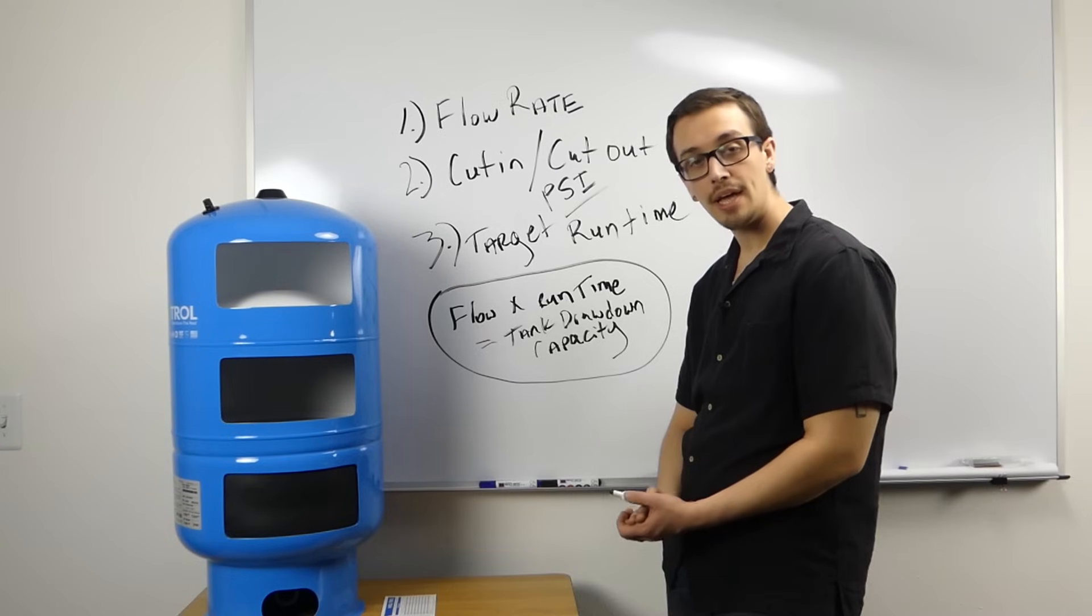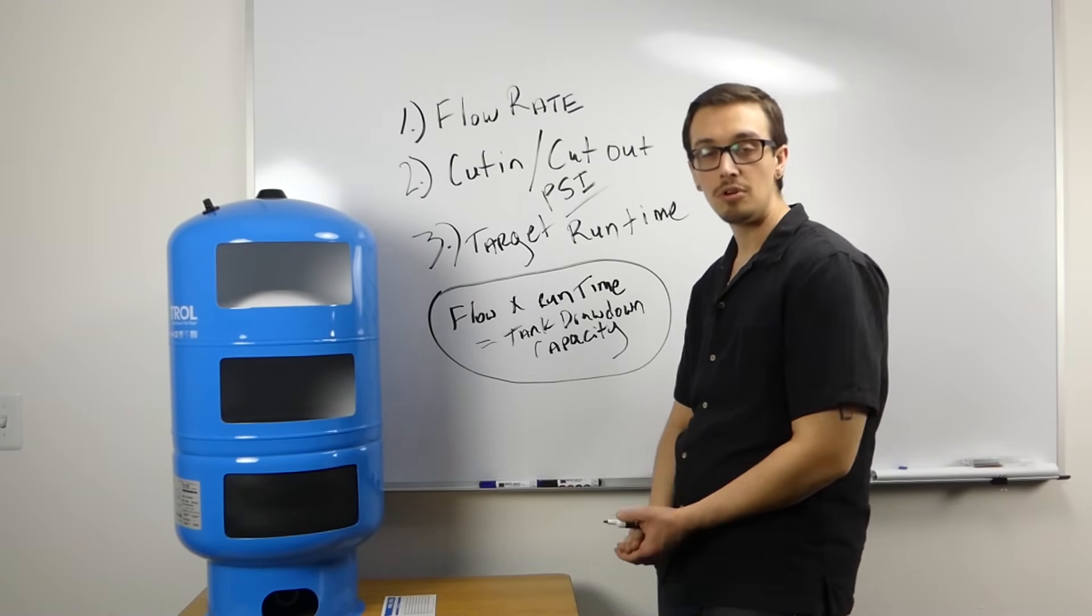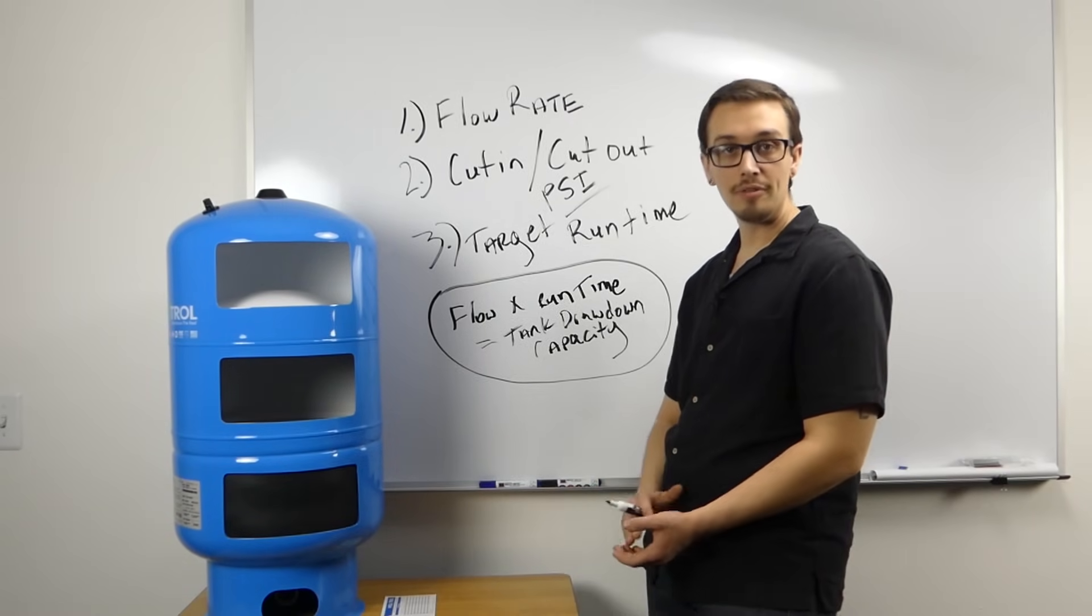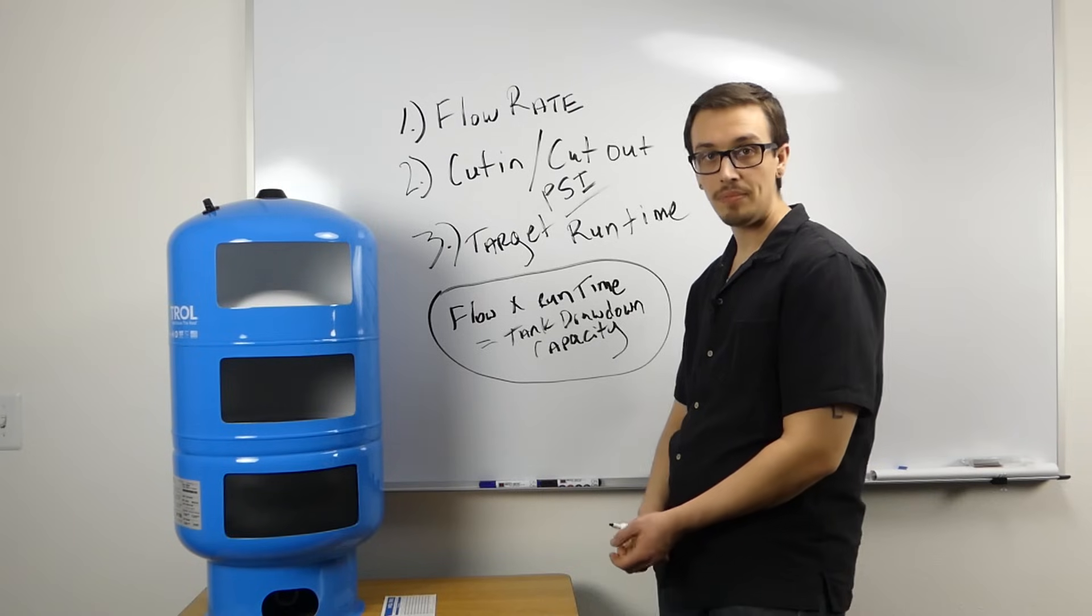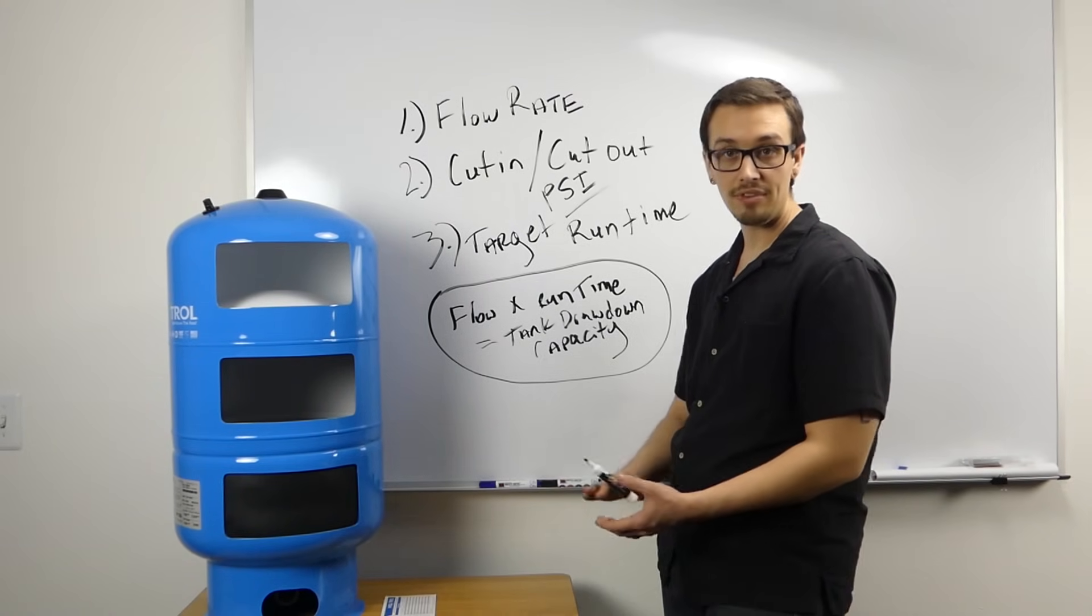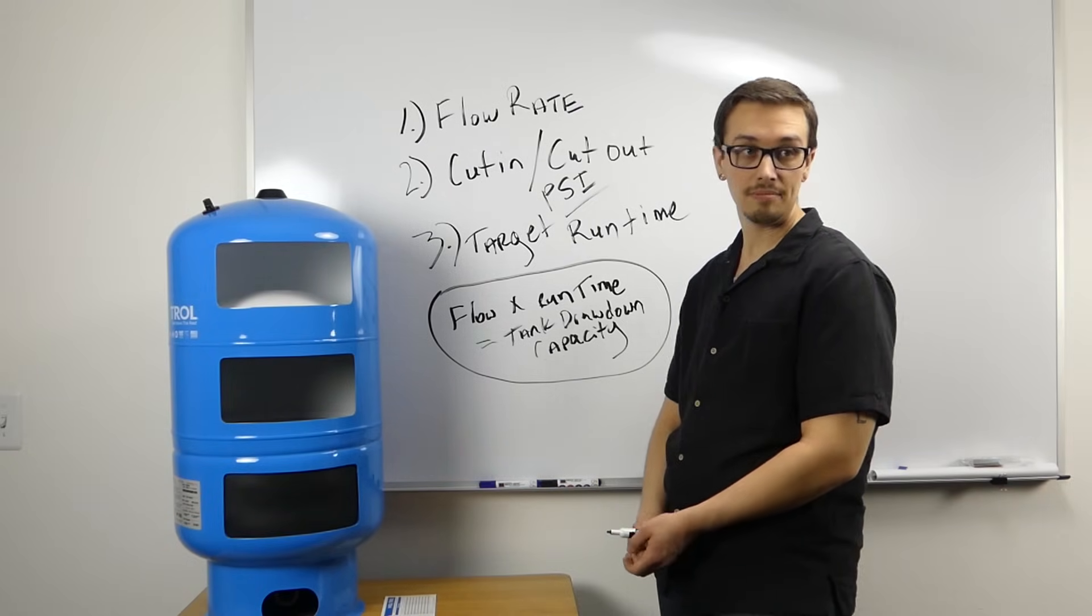Once you go beyond 20 gallons per minute, the rule of thumb is to double it. So for every gallon per minute of the pump, it would be two gallons of drawdown capacity. So a 25 gallon per minute pump would need 50 gallons of drawdown capacity.